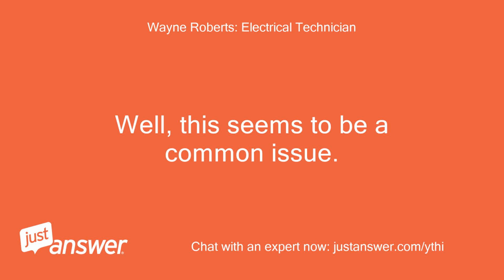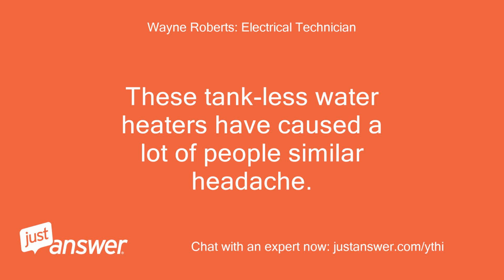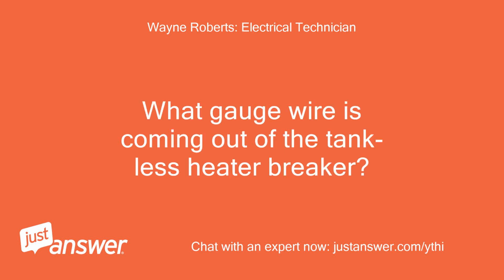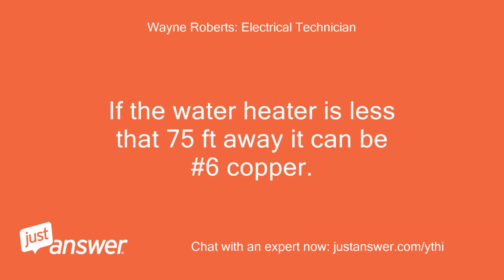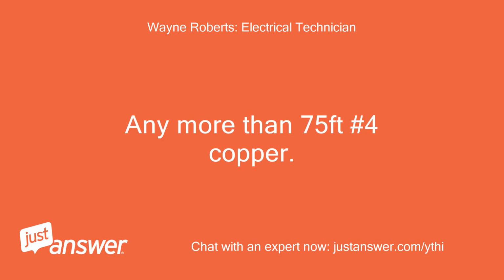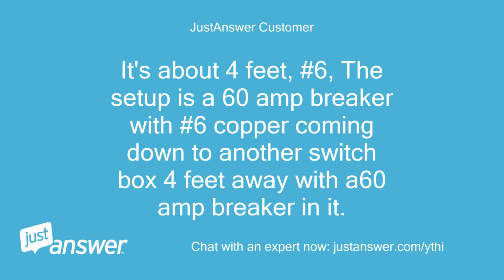Well, this seems to be a common issue. These tankless water heaters have caused a lot of people similar headache. What gauge wire is coming out of the tankless heater breaker? If the water heater is less than 75 feet away, it can be number 6 copper. Any more than 75 feet, number 4 copper. It's about 4 feet, number 6.